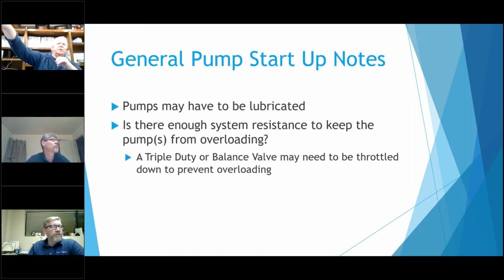But hopefully, if you've got a triple duty or balance valve, you can throttle that down, maybe to about 50% before you even turn the pump on, just to make sure there's enough resistance so that the pump doesn't run off the curve. So you want to watch out for that, especially on newer systems. On the old ones, or where you're just doing a pump replacement, you really shouldn't have to worry about that because it's already been balanced. You just open the valve back up to where it was before and go ahead and turn the pump on.